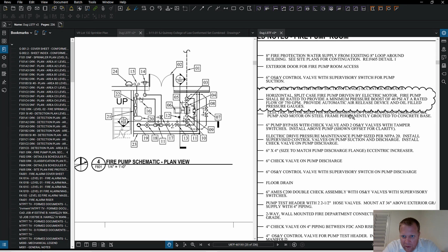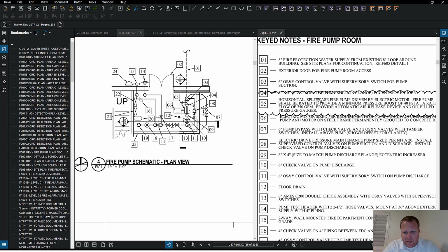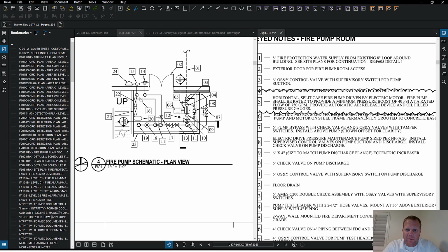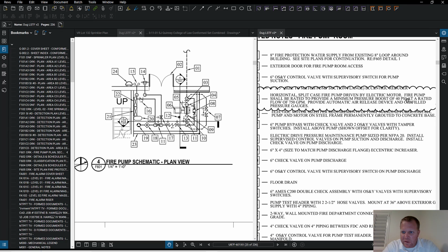Install pump and motor on steel frame permanently grouted to concrete base. There's going to be a concrete base right here with a fire pump on it. You have the electric motor, and then the pump is right here. And so number five is the pump, horizontal split case fire pump driven by electric motor. Fire pump should be rated to provide a minimum pressure boost of 40 psi at a rated flow of 750 gallons per minute.